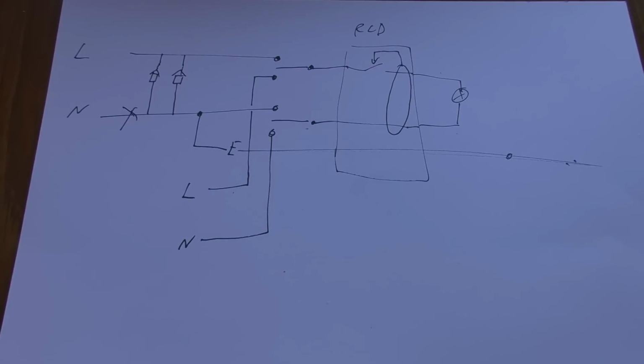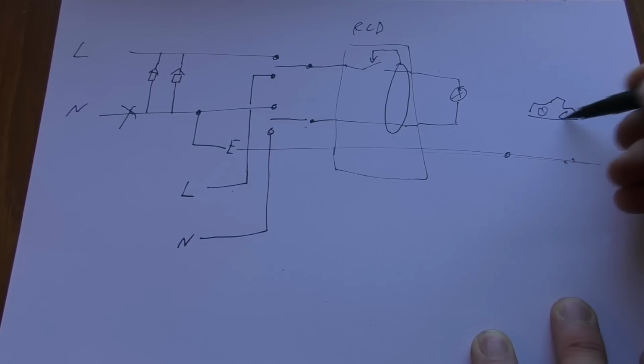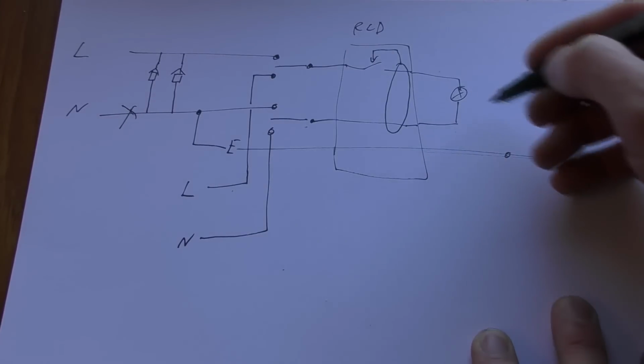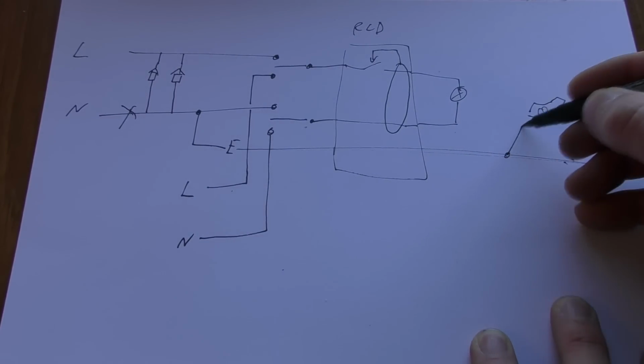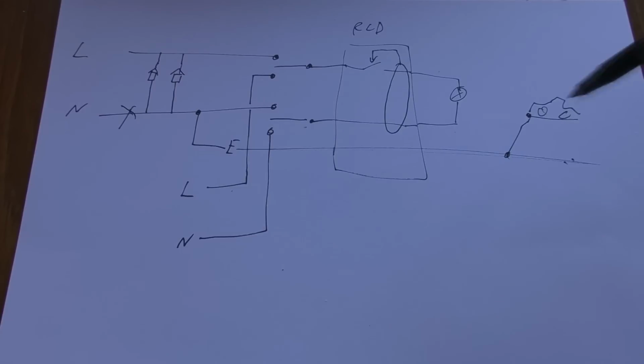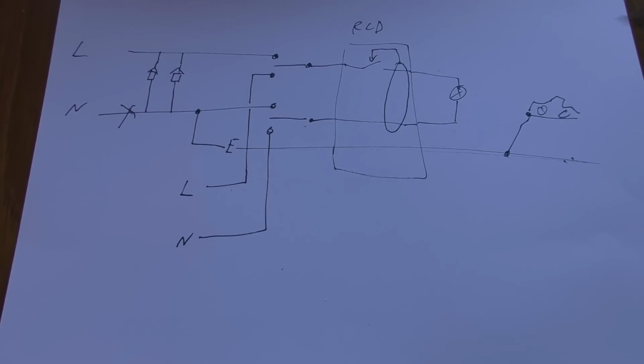Now this has been an issue with EV charging, where you've got your EV set outside charging, plugged into your EV charge point, and obviously the chassis of that is connected to mains earth. In the event of a PEN fault, effectively the whole car becomes live. Because that's generally set outside, there is a chance that you could touch that and current could flow, and that's why in the UK charge points have to have some means of protecting against that. There's various ways of doing that, but it basically detects that situation and disconnects the earth as well as the conductors.